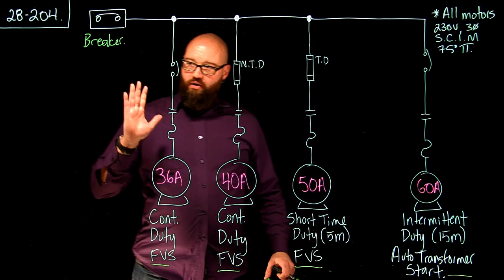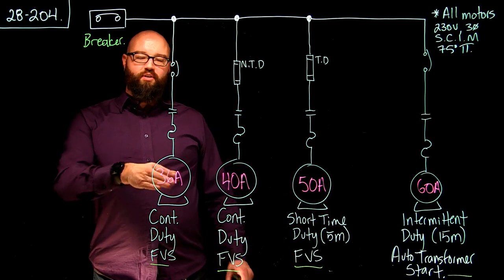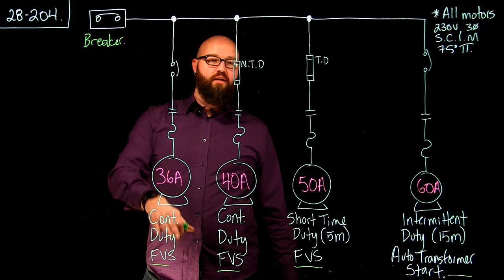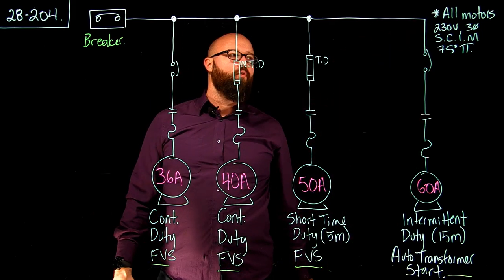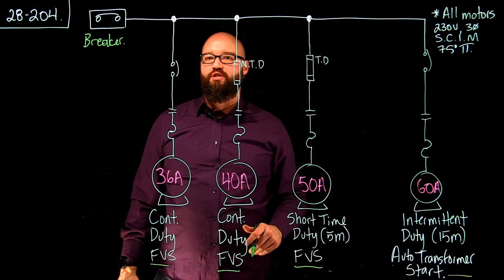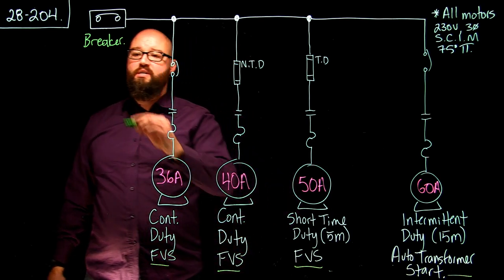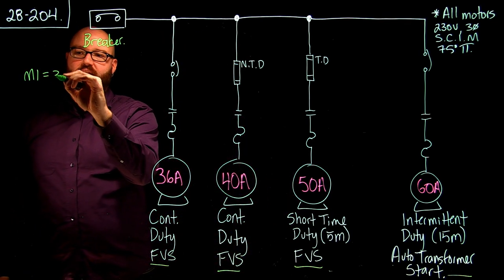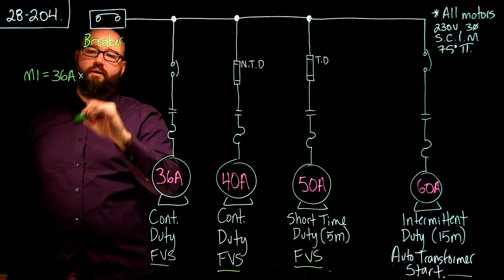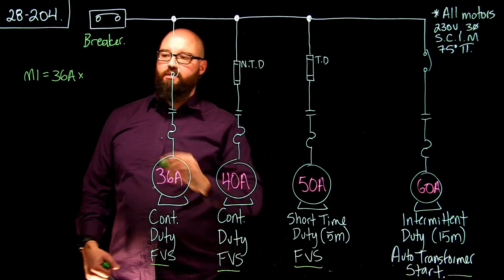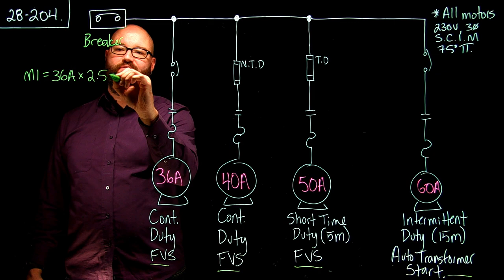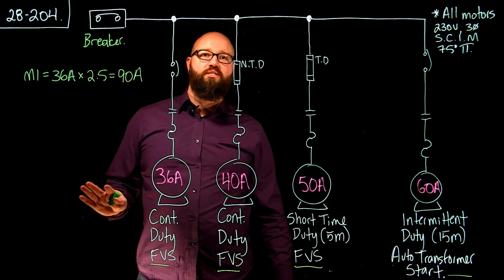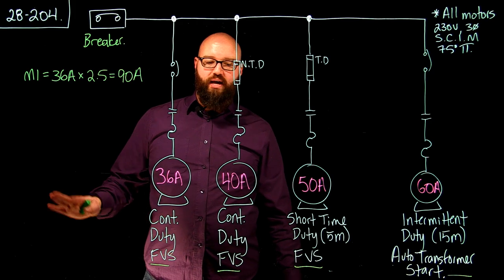Let's start with our 36-amp motor. I'm going to go to Table 29 and find, for a full voltage start, 230-volt, three-phase squirrel cage induction motor. Motor 1 would be 36 amps times 250% — that's 2.5 — giving me 90 amps. I'm not going to do anything with this number just yet.